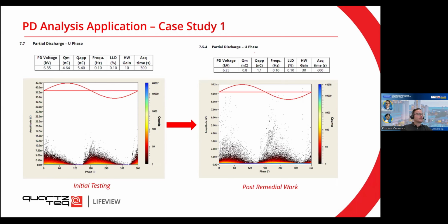You can see here that the scale is completely different. So this scale is 4 times higher on the left side. So it's around above 40. And on the right side, the scale is 10. So the partial discharge is decreased by a factor of 8, which means that the health of the machine was really improved. And now, probably, for the next few years, no additional work will be needed because these partial discharges are at a very, very low level.